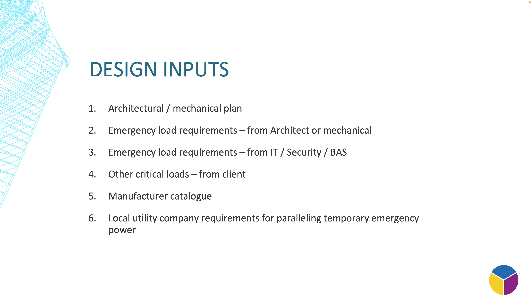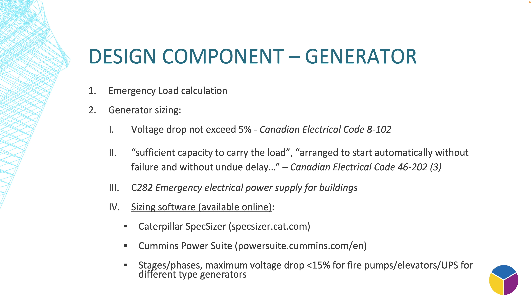Other loads include IT, security, BAS, and critical loads like healthcare project loads in the hospital. We also need manufacturer catalogs — once you get the generator size, you look at the catalog to find the weight and dimensions, then create a layout for your generator room. The last input is the local utility company requirement for paralleling or temporary emergency power, which covers the different generator operating modes.